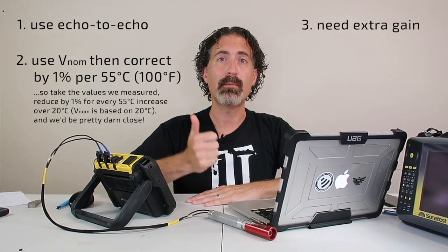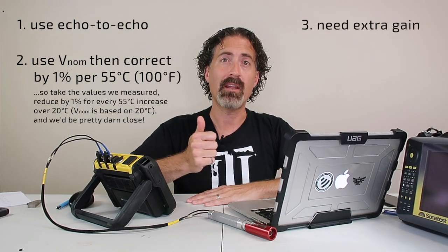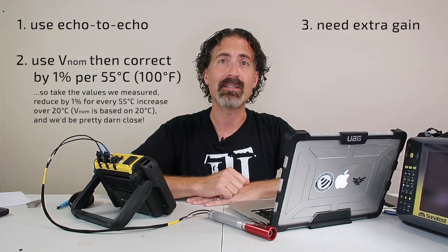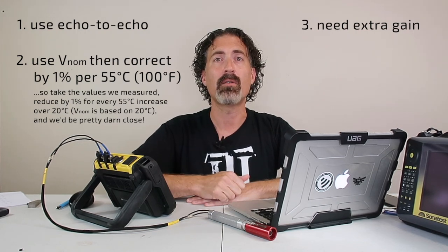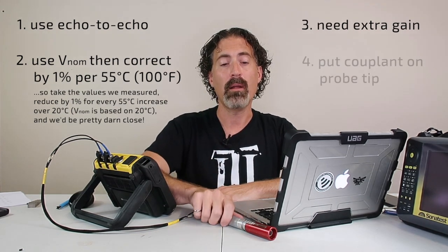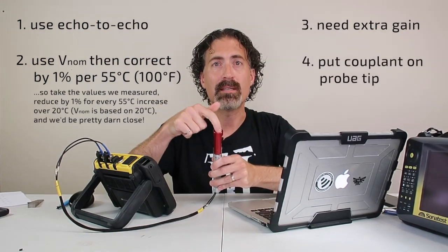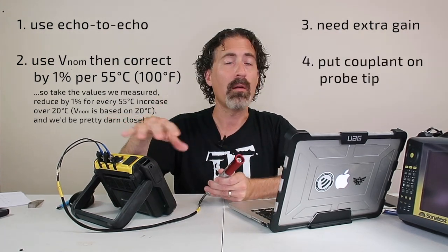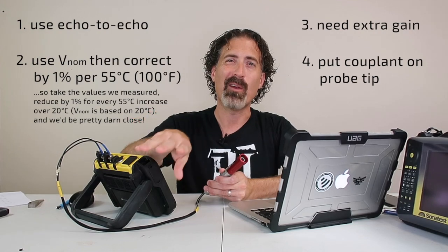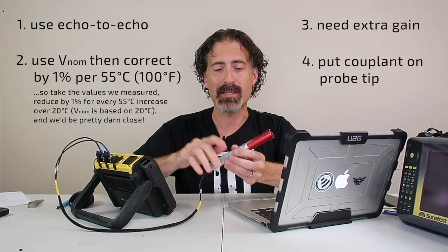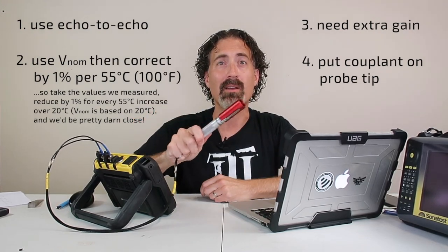Number 3, as temperature goes up, so does attenuation, and you're going to have to compensate by adding gain. So increasing temperature means increasing gain. And number 4, try to put the couplant on the tip of the probe. If you put it on the part, it works both ways. The thing is, you just get your hand really close to that really hot spot. And besides, that's why these probes have nice long handles.